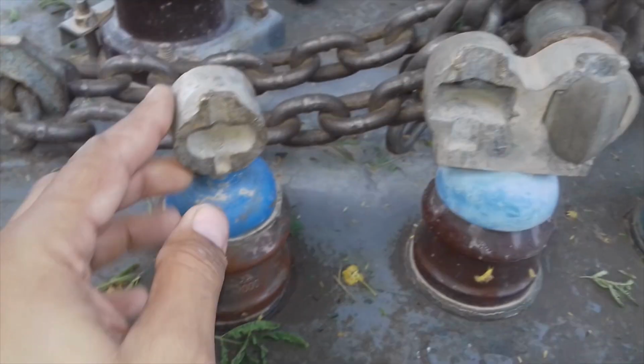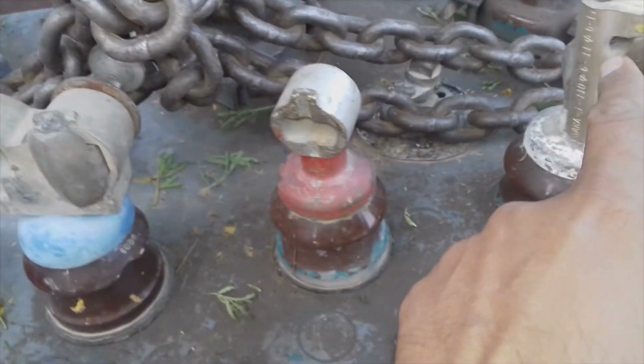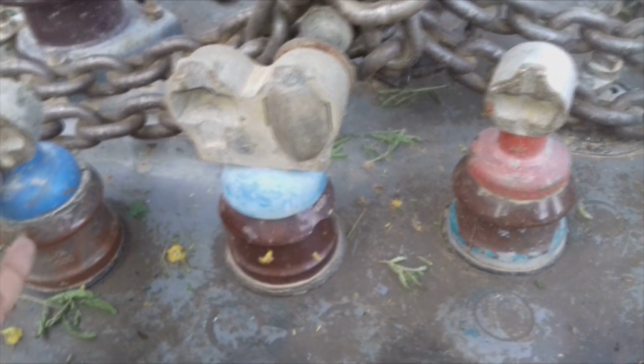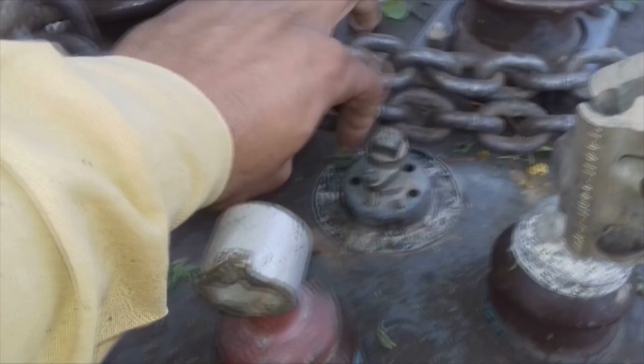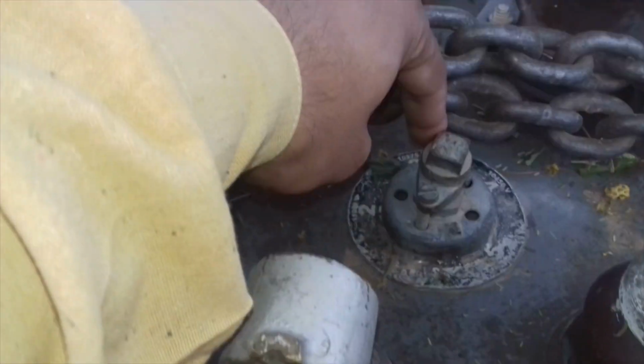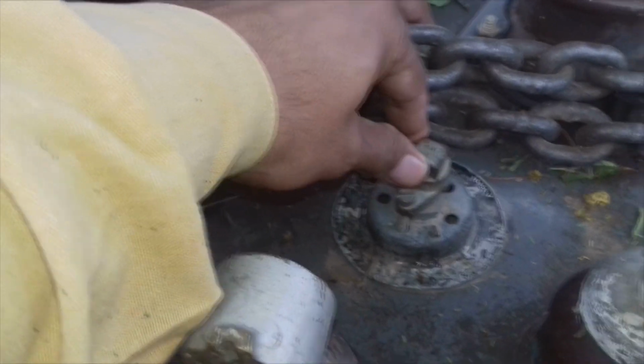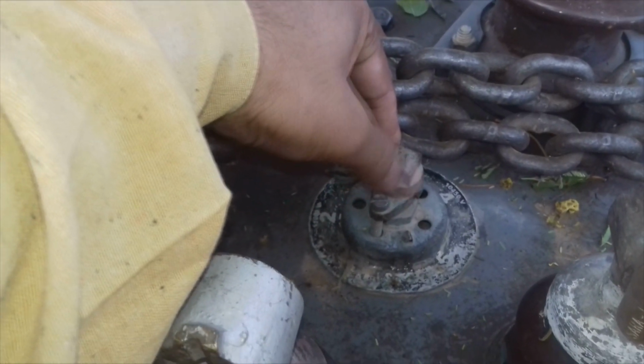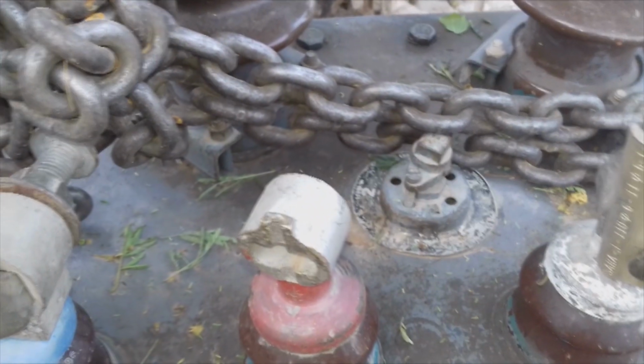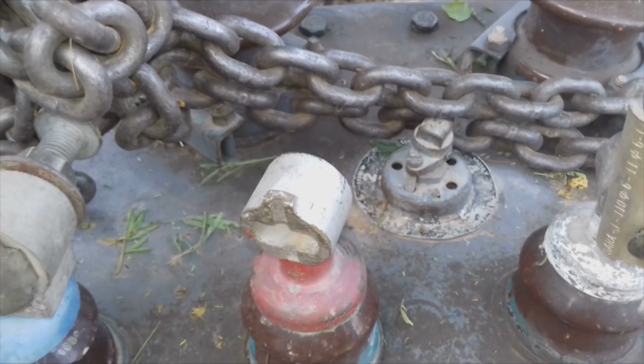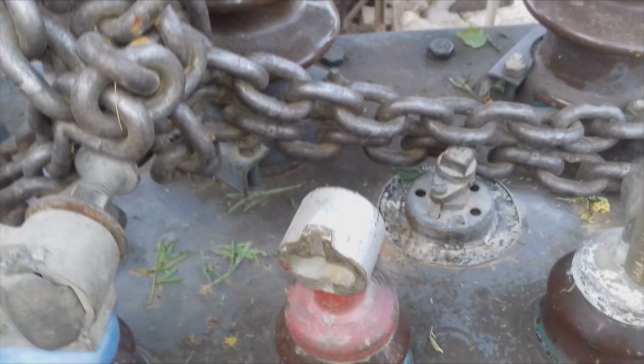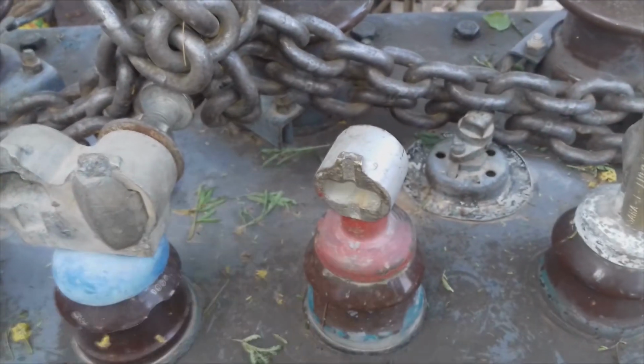So these are containing actually some 415 volts. So these are four in number. There is a neutral and there are three phases. So this is secondary. Secondary is connected in star, and here is this tap changer device. Underneath this nut, you can see there is a covering. Underneath there is a tap changer, but instead we can change it from here. Even if we open this screw, we can change it through some handle or some special service device, and we can change the tapping inside the transformer. So these are the details.